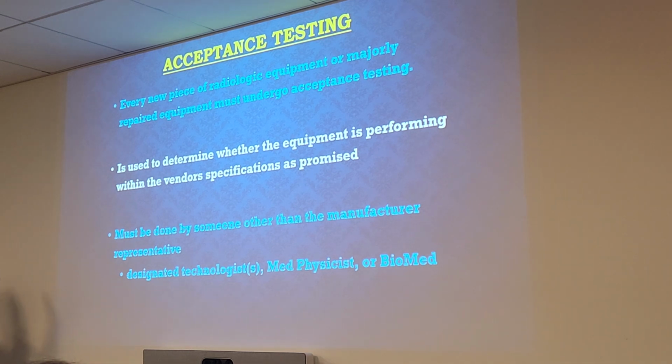Acceptance testing is done by the designated technologist, which is most likely your QC technologist, the medical physicist, and or biomed. So remember that. Acceptance testing has to be done by someone other than the vendor personnel or manufacturer representative. So either your QC technologist, medical physicist, and or biomed. Most likely, it'll be your medical physicist that does this. So any questions on acceptance testing?